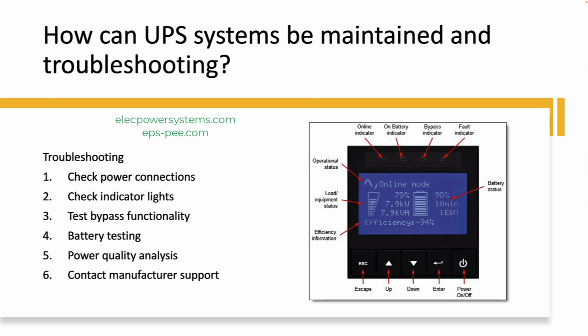Battery testing. Perform battery tests to assess their condition and capacity. This can be done using built-in battery testing features or with the help of specialized battery testing equipment. Replace batteries if they are faulty or do not meet the required specifications. Power quality analysis. If the UPS system is experiencing frequent alarms or failures, consider conducting a power quality analysis to identify any underlying power issues in the facility, such as voltage fluctuations, harmonics, or electrical noise.